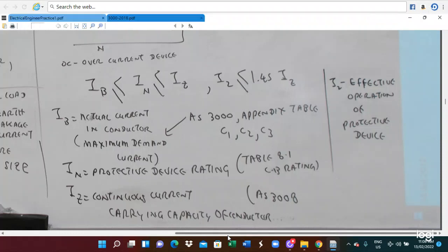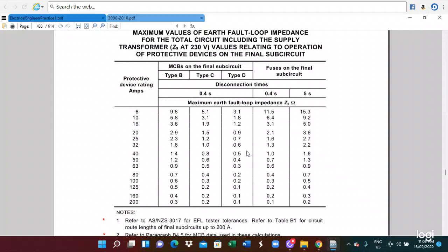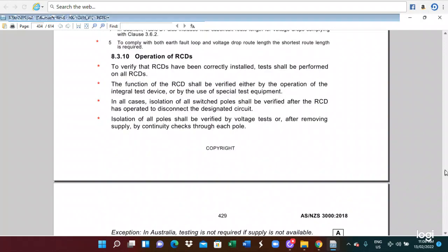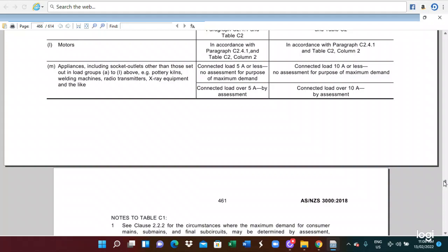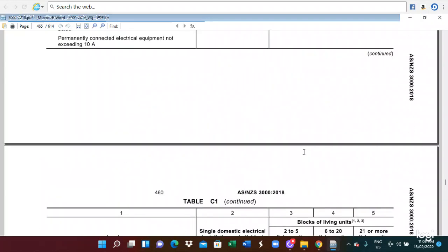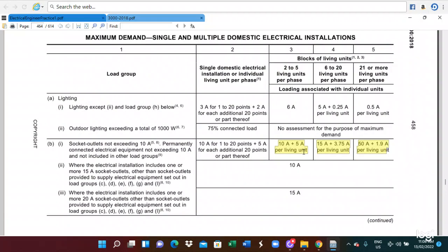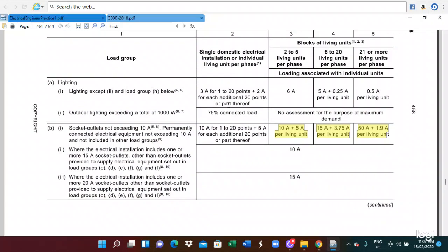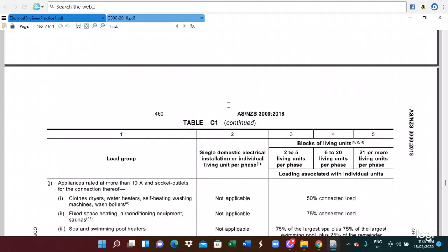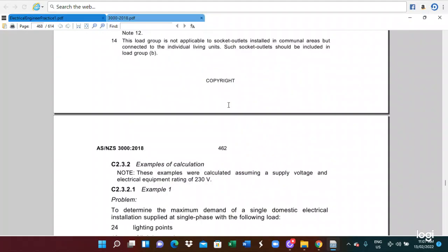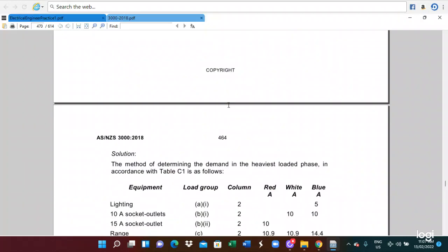The maximum demand current: we have to refer to the AS3000 appendix tables C1 to C3. Go and look at AS3000, and you can get tables C1, C2, C3. Table C1 is for the maximum demand calculation, depending on the lighting load, socket outlets, how many domestic electrical installations, how many blocks, and you can select the appropriate current. This is for the maximum demand calculation for domestic. And table C2 is for non-domestic installation.